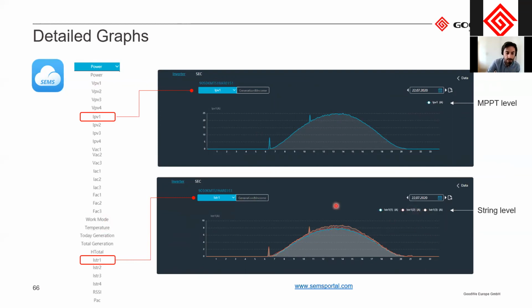So in case, let's say a customer has a fault of the inverter and they say it has problem connecting to the portal, then you can, for example, go in here and check the RSSI strength, which is the Wi-Fi strength of the inverter. And then you can check that, okay, maybe the Wi-Fi has a really weak signal, and therefore it has connection issues. So it's also a tool for installers to troubleshoot a specific plant without needing to go to the site directly.